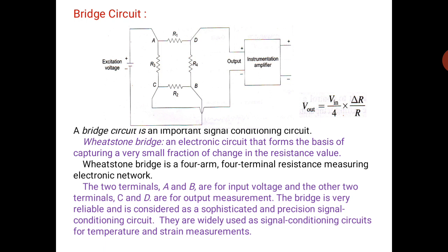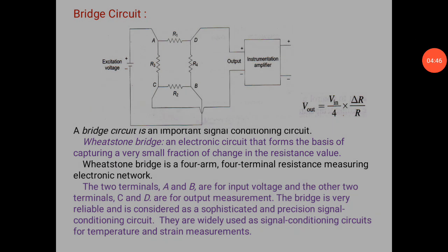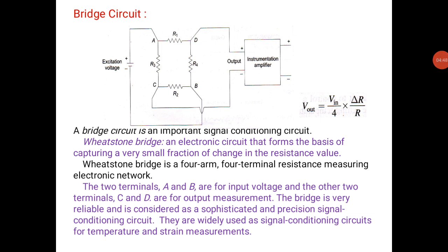The bridge is very reliable and is considered a sophisticated and precision signal conditioning circuit. They are widely used as signal conditioning circuits for temperature and strain measurements. Output of the bridge circuit is calculated as Vout equals Vin upon 4 times delta R upon R.